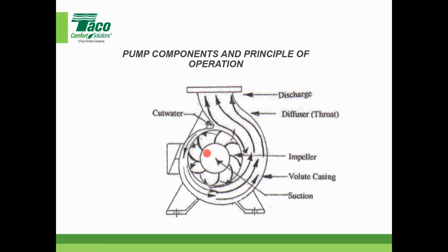So what that means, we call it trim, cutting it, whatever. That means you actually grind off part of the impeller to get a certain diameter, right? You have different diameters for the impeller. The maximum trim impeller will give you the best efficiency point, because your highest efficiency is when this clearance right here is as small as can be. Otherwise, as you make this clearance a little bigger, right? Think about it, you get a little more recirculation in there, and that causes some losses internally that will affect your efficiency.